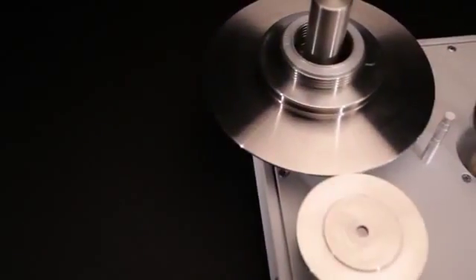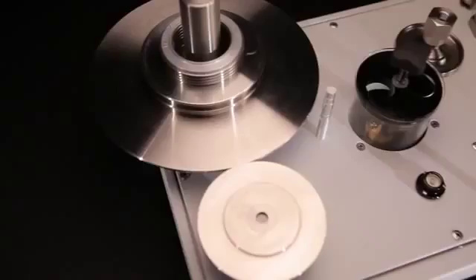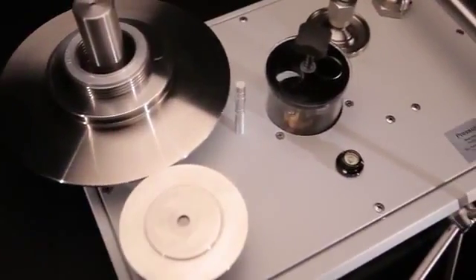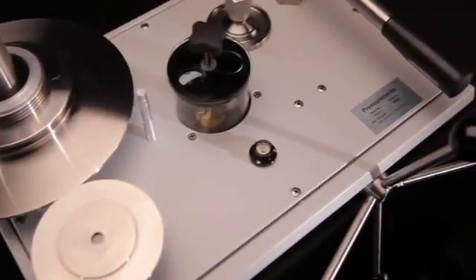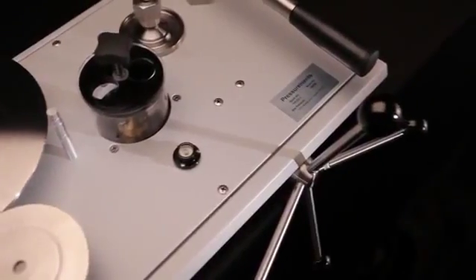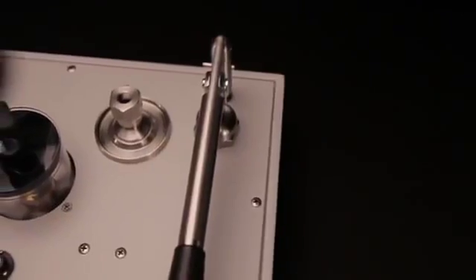The Pressurements hydraulic deadweight tester is available in a number of different configurations. The P3100 series is for use with mineral oil as the media. For applications where the use of oil as a media is prohibited, the P3200 series is available for use with water as the media.